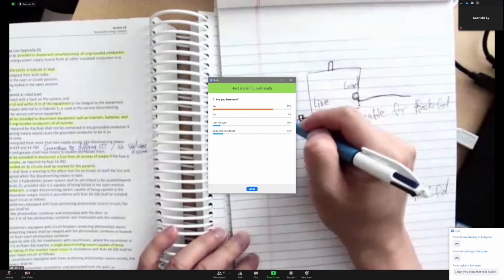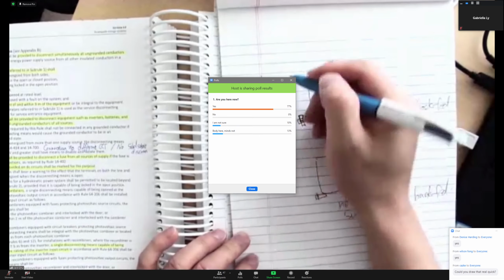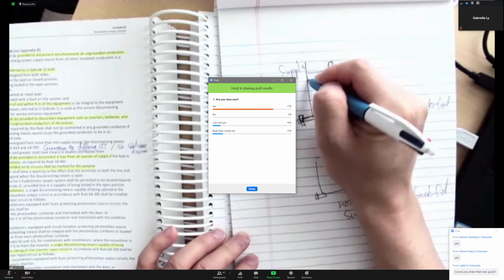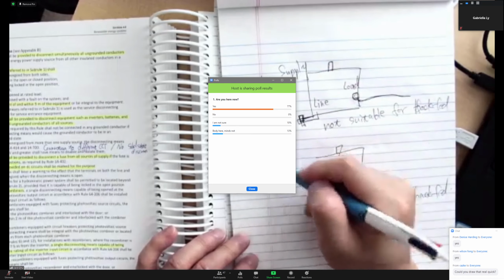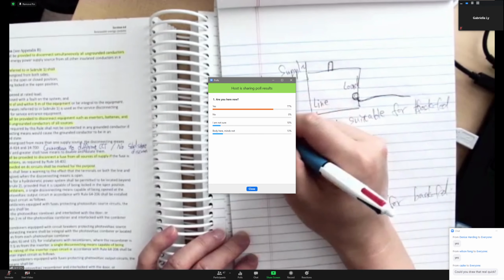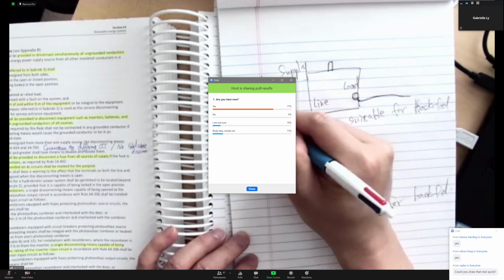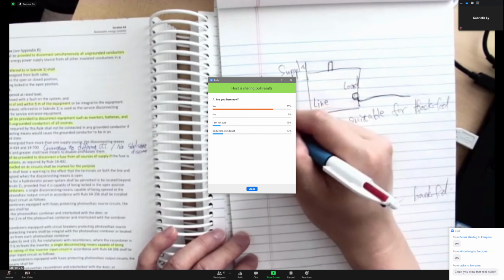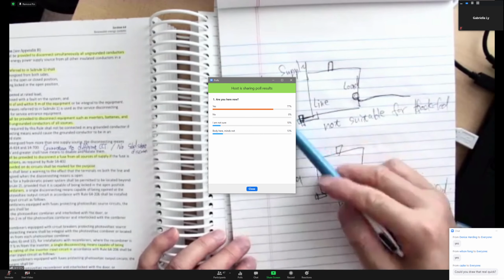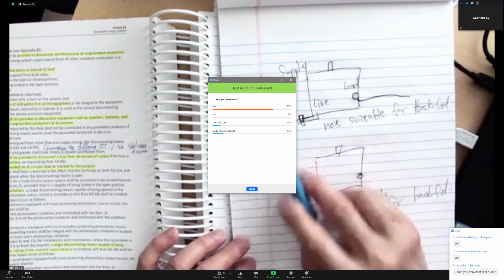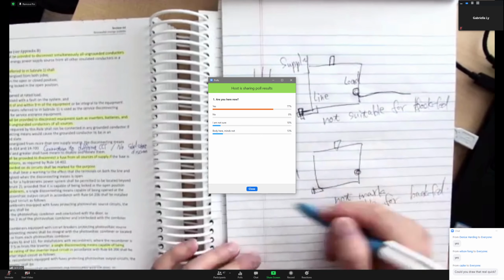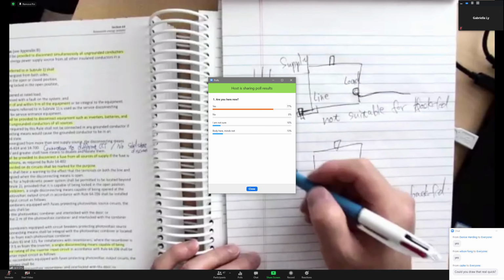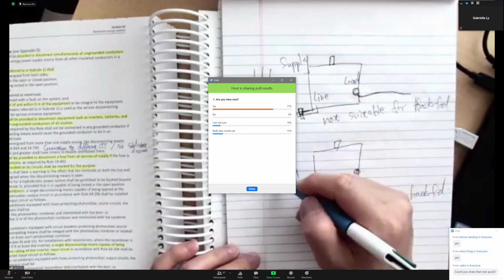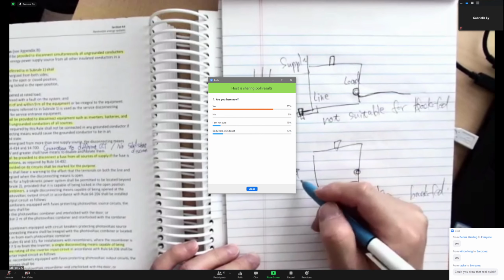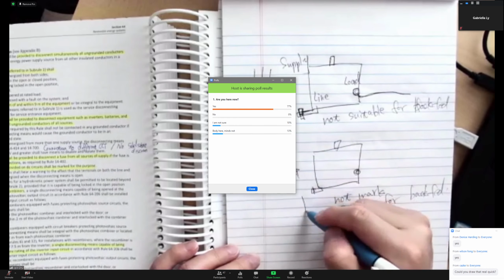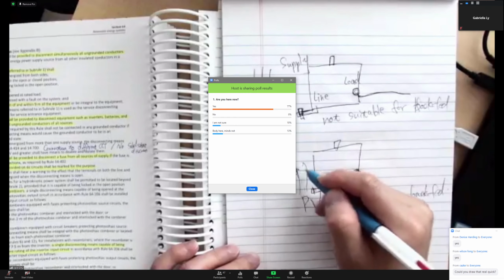A regular fusible disconnect: the supply has to come from the top, right? Your load connects on the bottom. The fuse is on there, but your blade is only, if you turn off the fusible disconnect, you're only going to disconnect the top. So what it requires is, if that's the case, you're using this for, let's say you have a PV system or whatever connected down here.